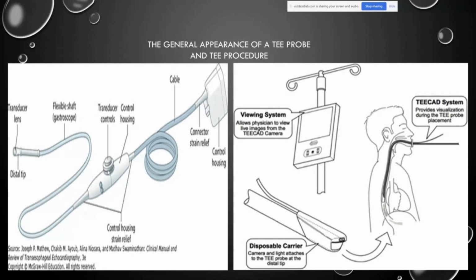So there are three main types of TEE probes. You have the monoplane, the biplane, or the omniplane. And the omniplane probe is sometimes called a multiplane probe. So let's talk about the monoplane probe for a minute. The monoplane probe has a single transducer that images in transverse, like at right angles. So like the 0-degree plane, basically. So that was the first one that was developed. But then they found out that there was an issue. So then the biplane probe was developed.